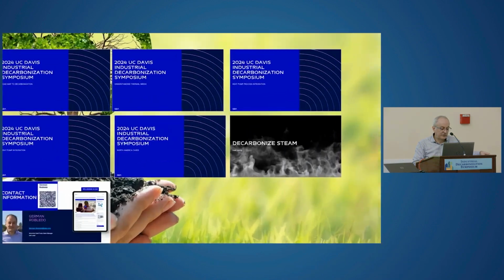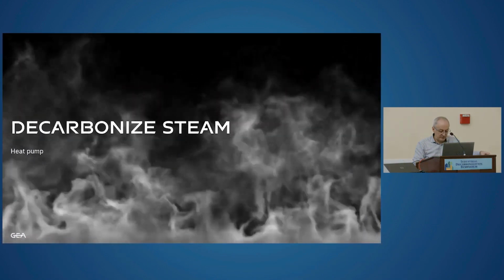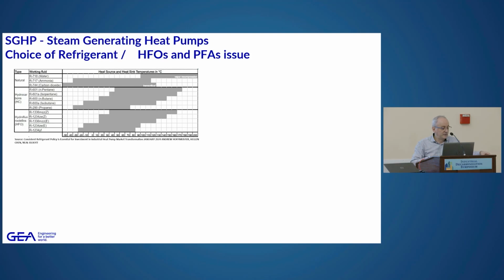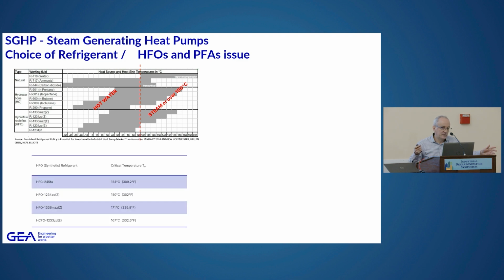So when it comes to steam, we can decarbonize steam. Basically, we can make steam with heat pumps. You're looking at different temperatures, making hot water temperatures and making steam temperatures. It all depends on what refrigerant you're going to use. When ACEEE came out with this report, they decided to define them between natural refrigerants, hydrocarbons, and HFOs. You can see the temperatures around these, depending on the critical temperature of that refrigerant, how high you can get to steam lines. HFOs, just to give you some context, can give you these high temperatures.